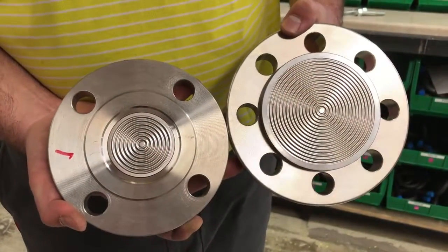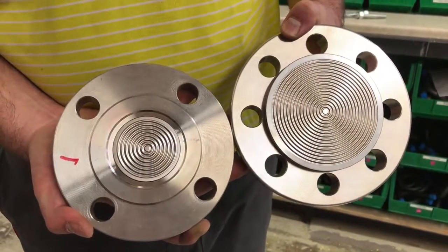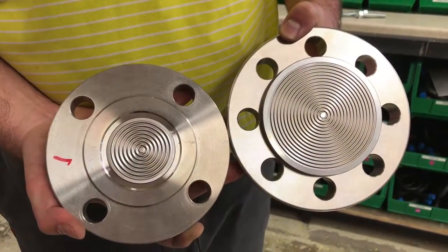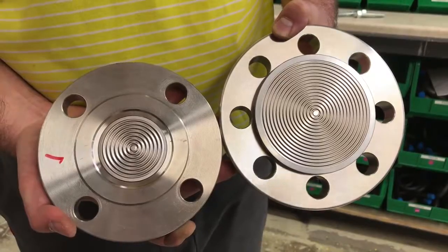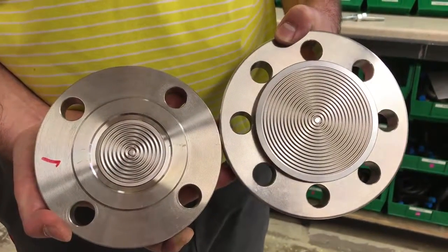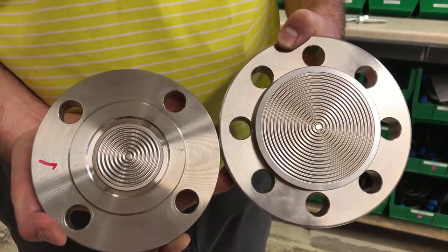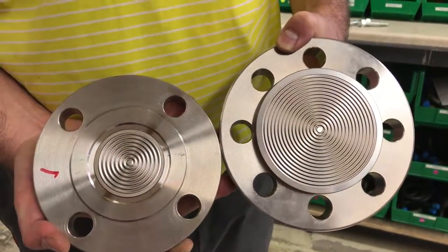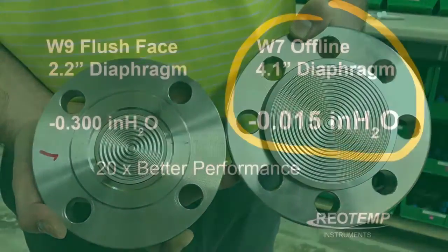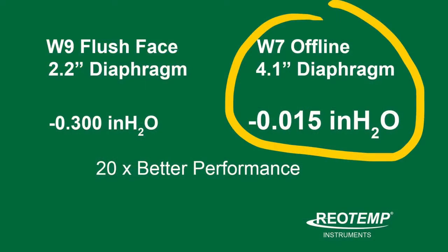The W7, with its 4.1 inch diaphragm, has an effective surface area three and a half times larger than the flush face seal. That added surface area makes the diaphragm much more sensitive and more able to absorb fill fluid expansion without exerting a false pressure onto the transmitter sensor.